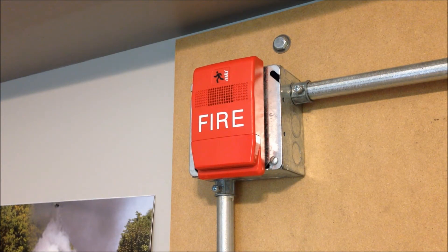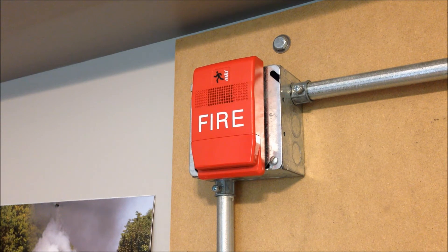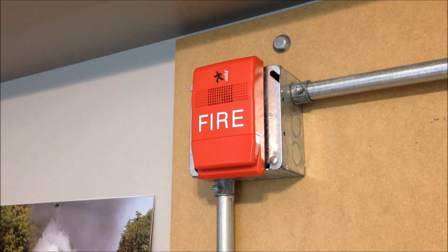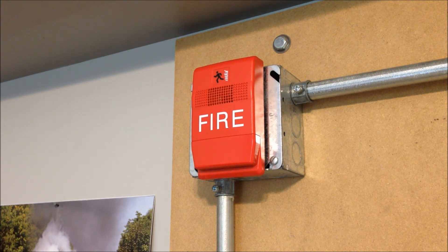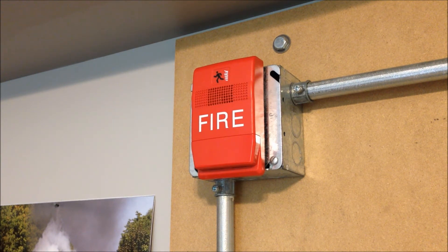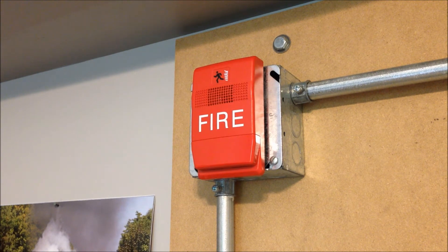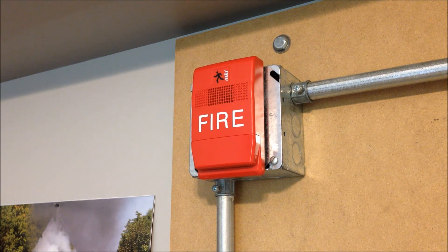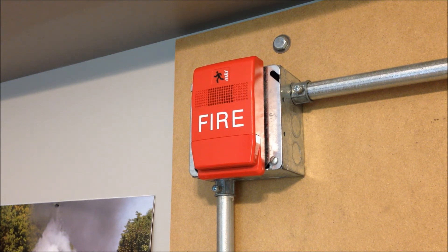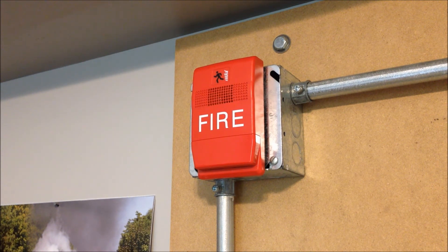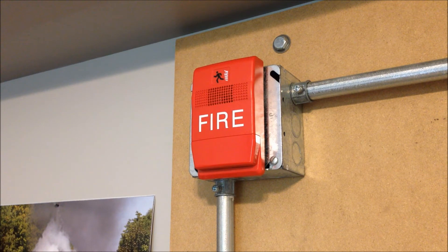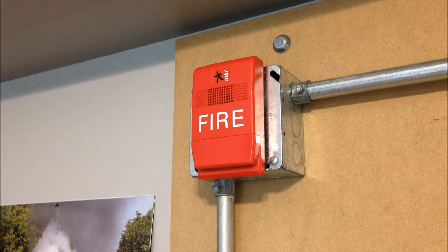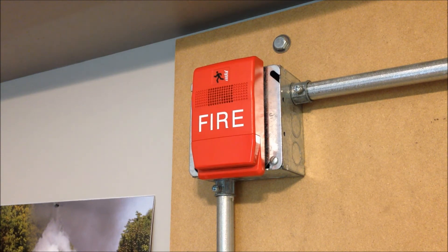Over on the NAC-1 spot, we have another first for my system test videos, which is the inclusion of a chime rather than a standard electronic or electromechanical horn. So, this is an EST Genesis model G1RF-C chime, and this is currently set on vibrating chime, which basically means that it will pulse out one of the chime noises on exactly one second intervals. And it's actually kind of interesting because this keeps very good time with the one second flash pulses of the Gentex Commander 3 strobe. That will be interesting to look at when we move back over to the smoke detector and set this system off in a minute or two.